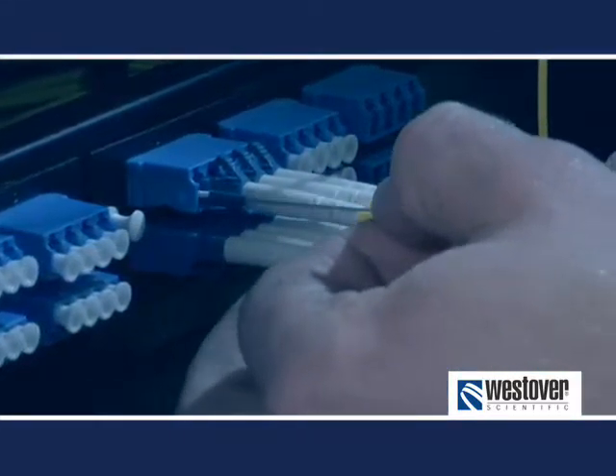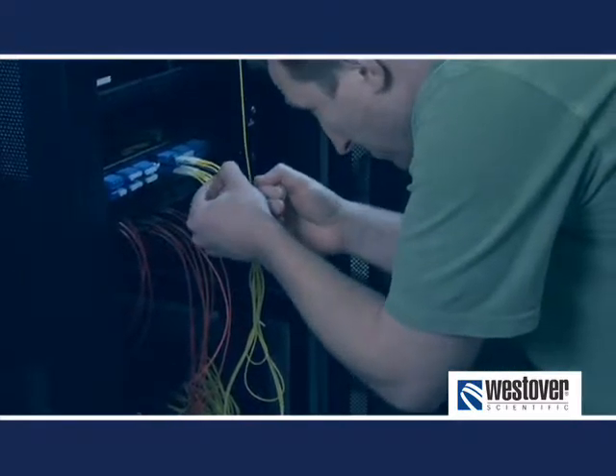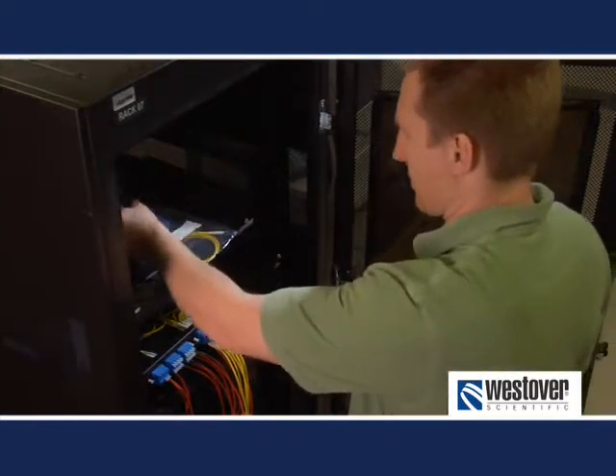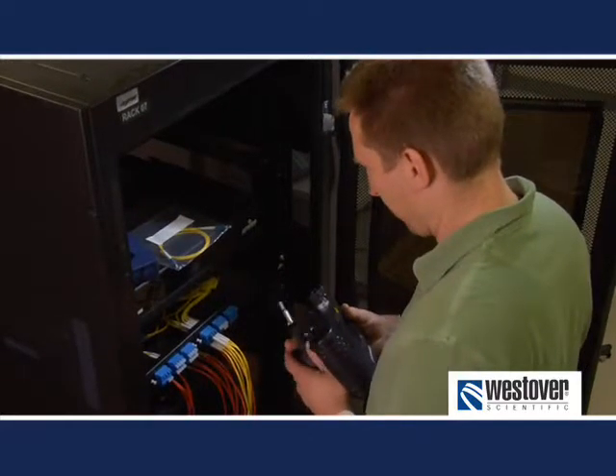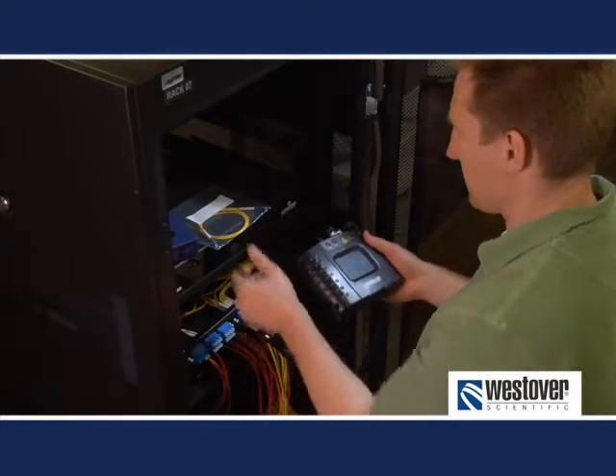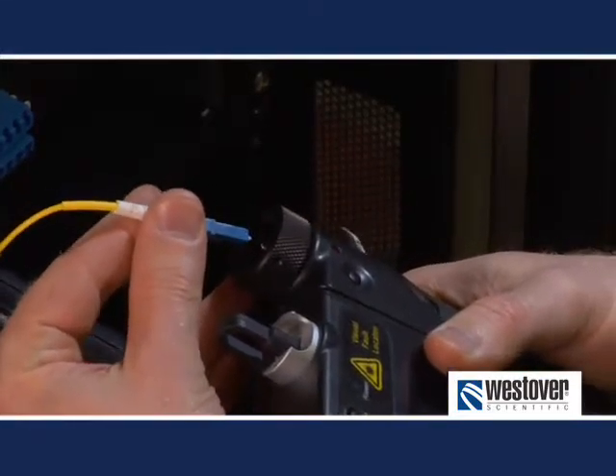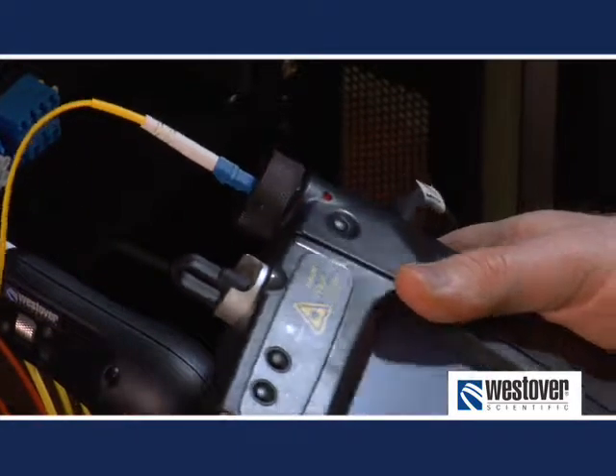Tier 1 providers estimate that at least 40% of troubleshooting optical connectivity is simply a result of dirty connectors, making this one of the most costly problems associated with fiber deployment and a major source of delay and downtime. A little dirt really can impact your bottom line. Today, the most progressive companies mandate proactive inspection and cleaning prior to mating the connectors. These companies have done so for two primary reasons. First, proactive inspection and cleaning is proven to drastically reduce troubleshooting time in manufacturing and field installation. Second, a proactive approach ensures that you're able to protect your company's assets by minimizing damage from mating dirty connectors.